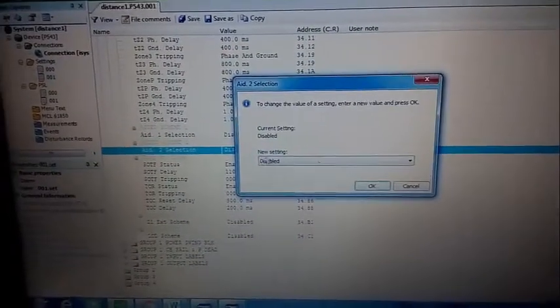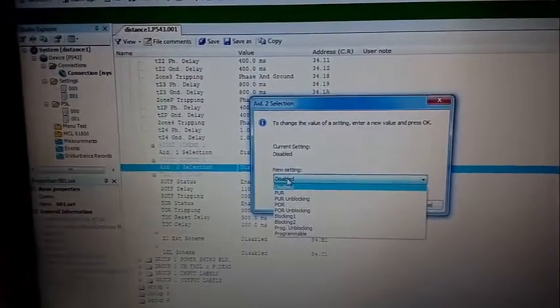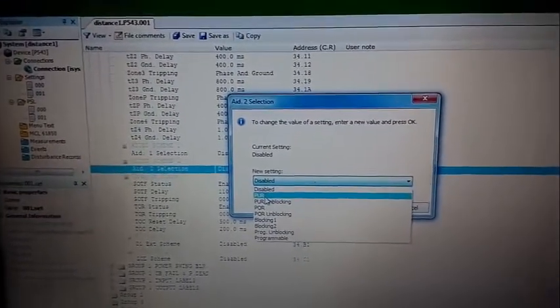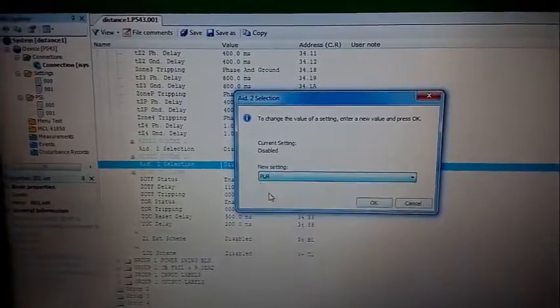Previously, the selection scheme was disabled in the without-communication mode. Now we will enable the Permissive Under Reach scheme. We go to edit value, select 'Permissive Under Reach', and save.